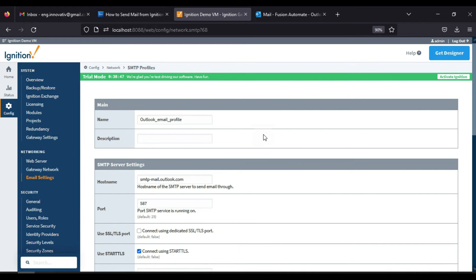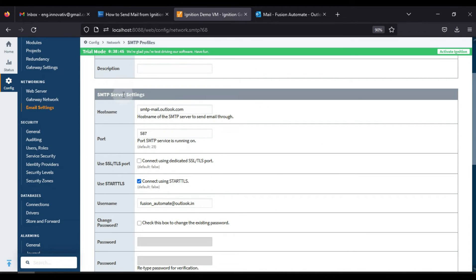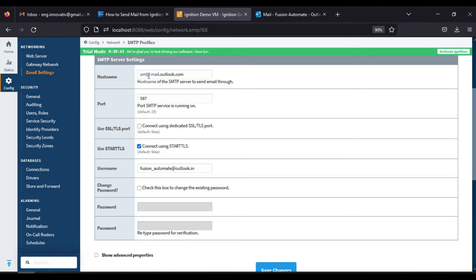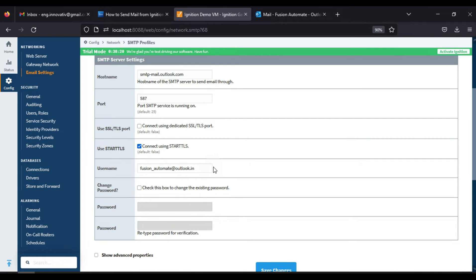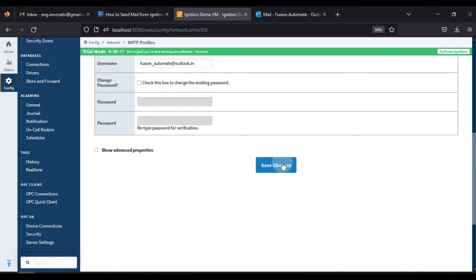Let me go to edit to see my settings. This is my email profile name. The main part is the SMTP server settings. The hostname for Outlook is smtp-mail.outlook.com, with port 587. Enable the 'connecting using StartTLS' option, then enter your username (your email address you will send from) and your password. The password fields are currently disabled because I already have my password stored inside Ignition.